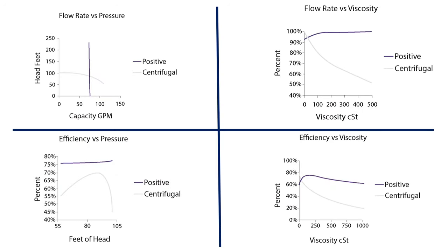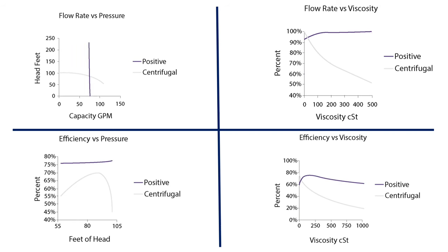For visual reference of the performance comparisons between the two working principles, see the performance curves below showing how both centrifugal and positive displacement pumps' duty are affected by different factors. For example, positive displacement pumps are able to handle variations in pressure, flow, and viscosity and remain efficient, unlike centrifugal pumps which do not operate well away from the center of their curve.